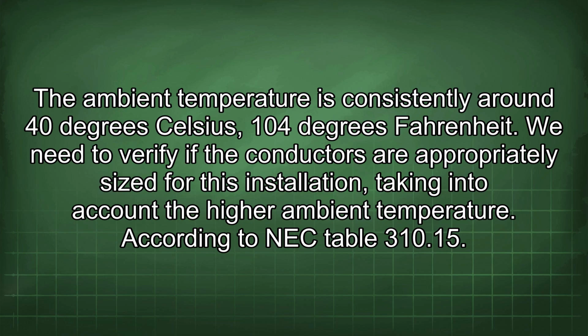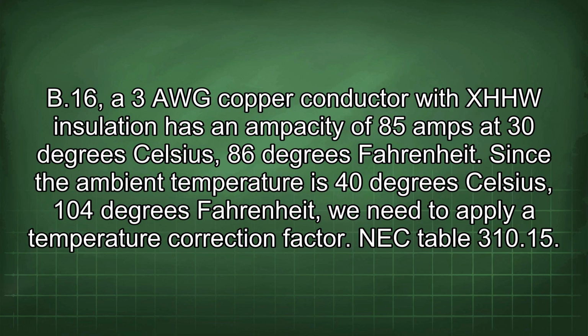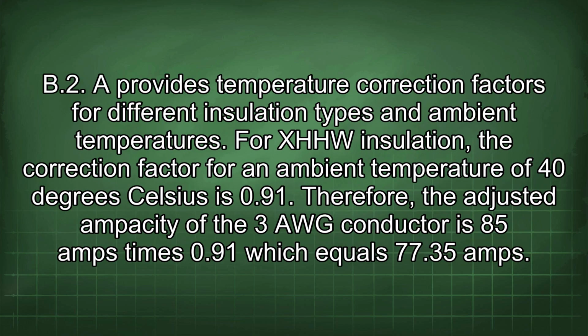According to NEC Table 310.15(B)(16), a 3 AWG copper conductor with XHHW insulation has an ampacity of 85 amps at 30 degrees Celsius, 86 degrees Fahrenheit. Since the ambient temperature is 40 degrees Celsius, 104 degrees Fahrenheit, we need to apply a temperature correction factor. NEC Table 310.15(B)(2) provides temperature correction factors for different insulation types and ambient temperatures. For XHHW insulation, the correction factor for an ambient temperature of 40 degrees Celsius is 0.91.